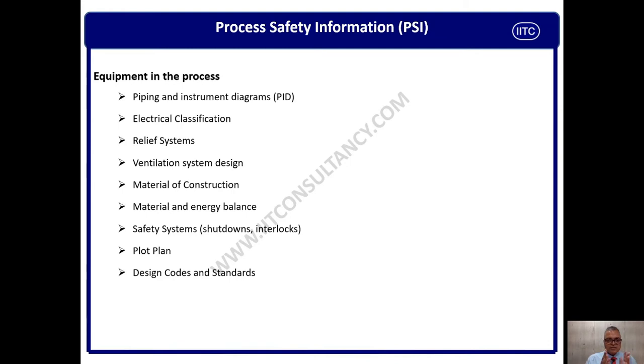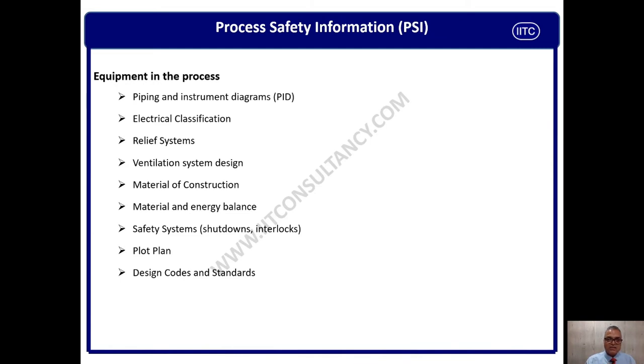Equipment must have relief systems — maybe PSV, process safety valve; PVSV, pressure vacuum safety valve; rupture disk; explosion chamber; or other means of relief of pressure. The ventilation system must be designed to ensure that all chemicals which are in excess as per the ACGIH, or as per the TLV and TWA, have a perfect efficient ventilation management system so that people working in the area are not affected by those chemical properties.